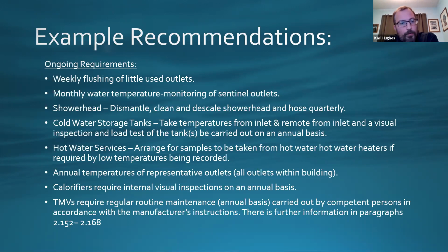And what we've mentioned before, the thermostatic mixer valves that blend the water, we've got to look inside them. So on the hot side feed and the cold side feed, there'll be little strainers in there. So you take them apart, check the strainers and clean them all down. You'd also do a fail-safe check, which is basically you would turn the cold water off to the mixer valve, and at that point, the hot water at the tap should start going off when it gets to its highest temperature and things like that.